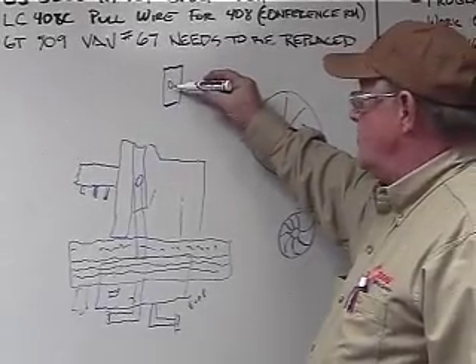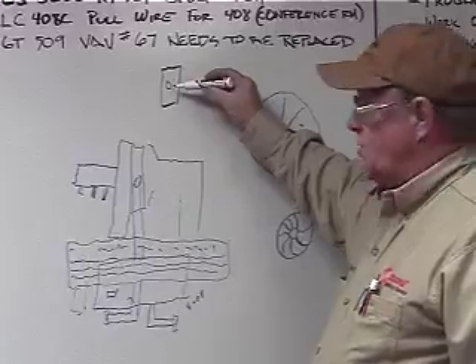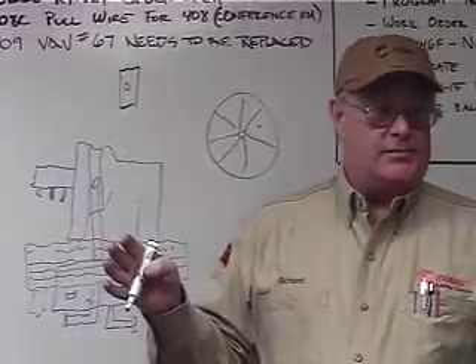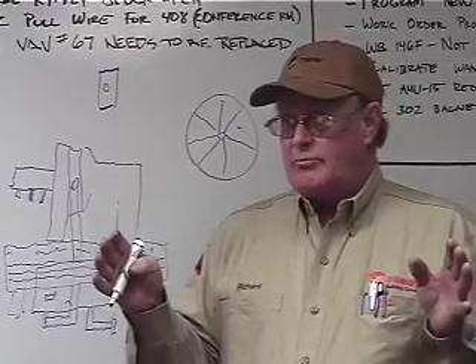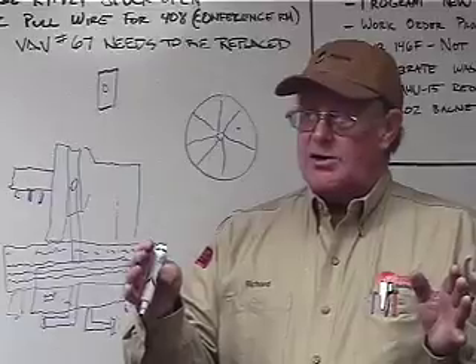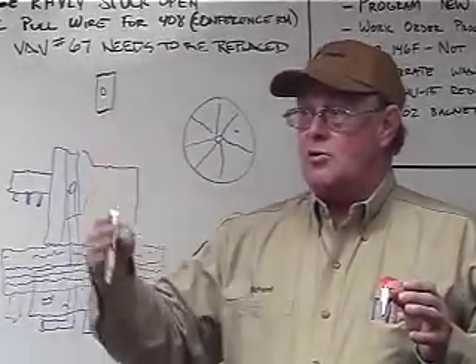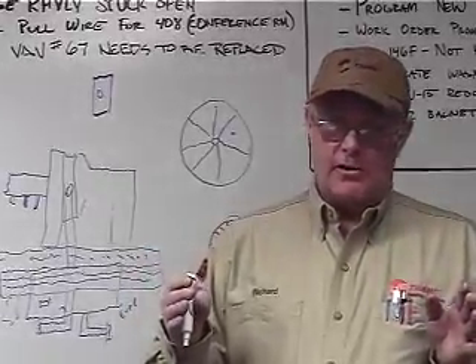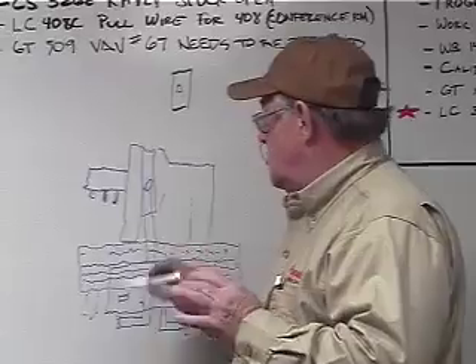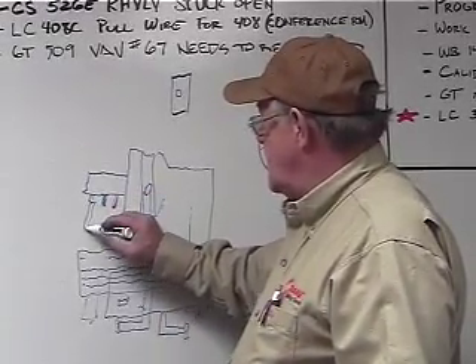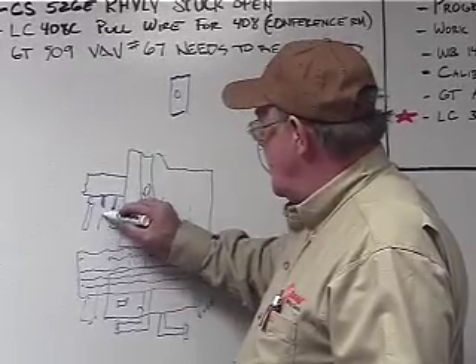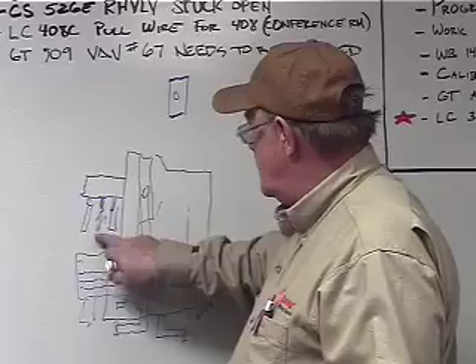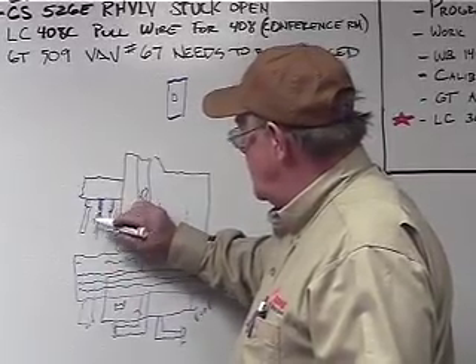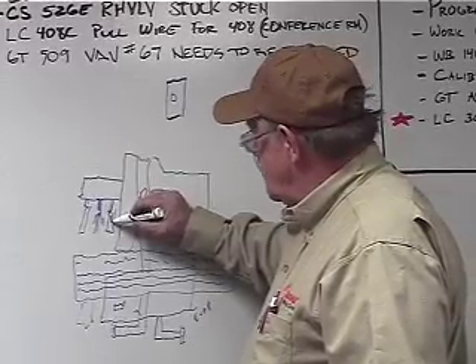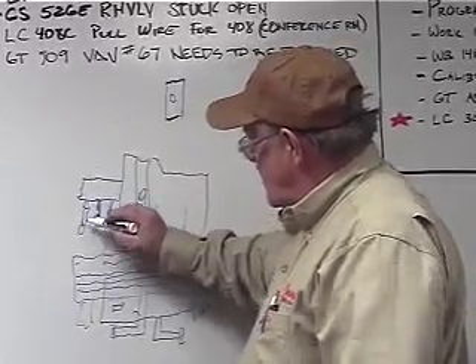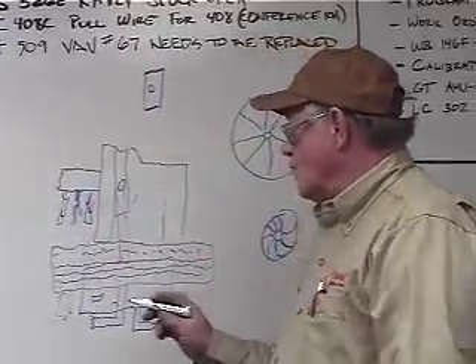What happens is your liquid refrigerant gets up here, and it's pushing the refrigerant through that little hole, and it flashes. When it's doing this flashing effect, basically it's creating cool gas to go over the motor windings. So that's how we get our motor cooling on this. As the gas is cool, we get the same effect. These lines come back down. We've got entering going this way. Entering refrigerant, and then it leaves going out this way and goes back down into your evaporator and your condenser.